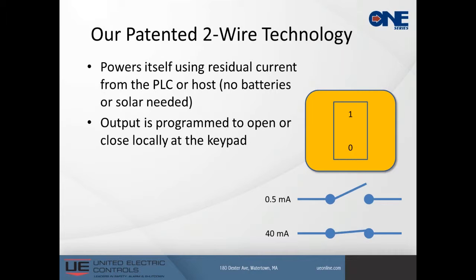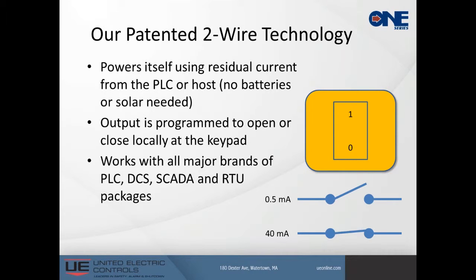The output is programmed to open or close just like a mechanical switch, but it's done at the keypad as opposed to an external source like a wrench and nitrogen and a test gauge to accomplish that. It works with basically all major brands of PLCs, DCS, SCADAs, RTU packages, interposing relays, solenoid valves. The key factor that you have to pay attention to is the minimum voltage requirements when you're starting to switch interposing relays and solenoid valves. But as far as any other major brand of a PLC, DCS, SCADA, RTU, we work fine.